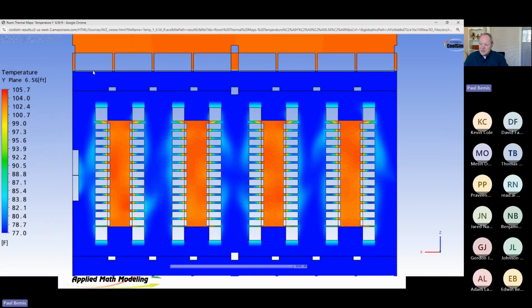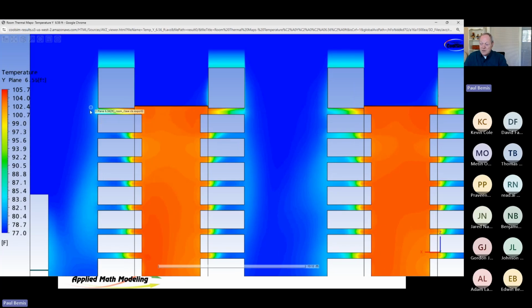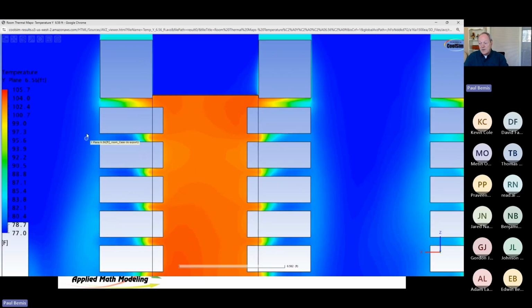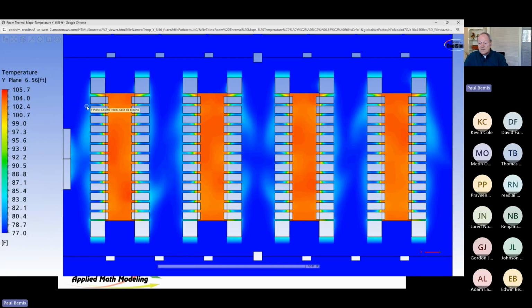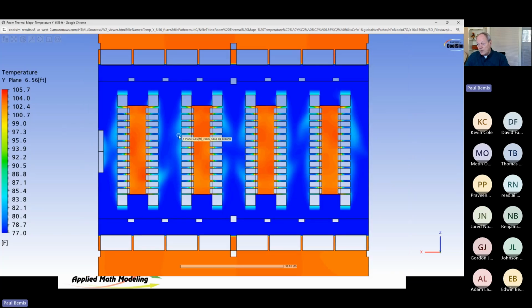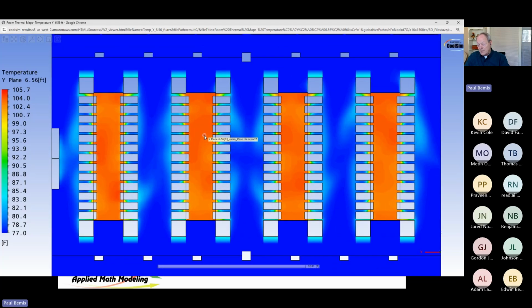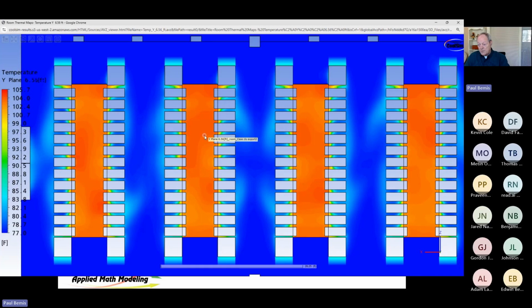Why? Because velocities here are high. As the air comes around this corner and past this rack row right here, I've got a low pressure right there compared to here. And what it does is it pulls the air through the gap and causes leakage to occur. Now, I could tell by looking at the RTI number that this was going to have a problem. That's why these parameters are important, because you can tell by looking at a single number. That's why they did it. They wanted to show that leakage parameter in an RTI pretty easy. And you can see this one's leaking pretty badly.